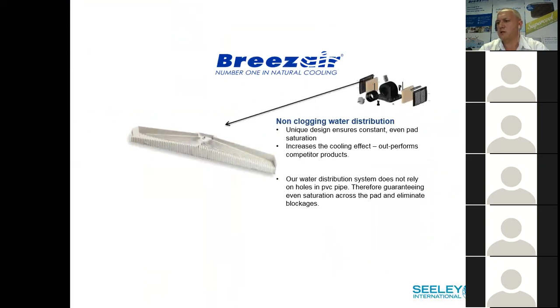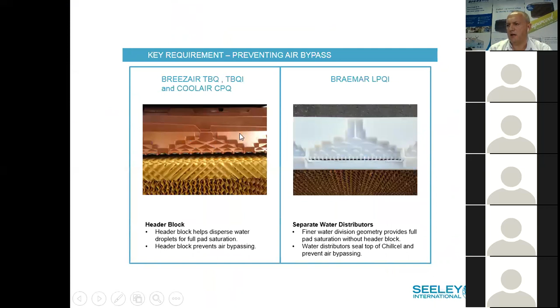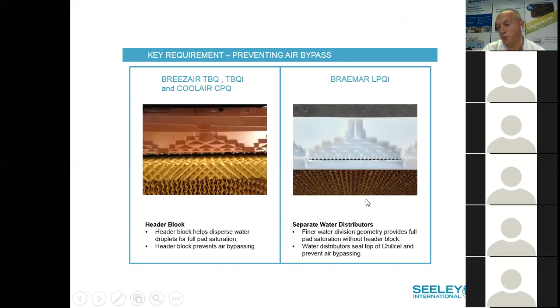The TBQ, TBQI Coolair CPQ range, as you know, has the spreader in the tank itself, and it has a header block. The header block is there to spread the water across the filter pack horizontally, and then vertically it'll go down through the filter. On the Braemar LPQI, it has a new pressurized water distribution system. It's a much more finite water distribution on the top. So it has separate water distributions across to each section of the filter. And you get proper full pad saturation without a header block. So you can actually increase the size of the filter. What we do, we've increased the size of the main filter to get you extra cooling.